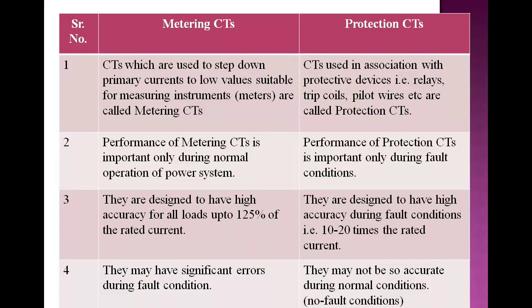Metering CTs are designed to have high accuracy for all loads up to 125% of the rated current. Protection CTs are designed to have high accuracy during fault conditions, that is, 10 to 20 times the rated current. Metering CTs may have significant errors during fault conditions, while protection CTs may not be so accurate during normal conditions.